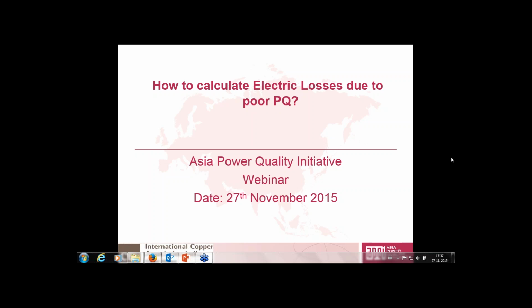Frank, this is for you. From an energy auditor's perspective, how do you calculate the losses due to harmonics and unbalance at any PCC in an industry? Well, the first point is to discover, using something like the unified power method, how to break down into each of the separate components. That's the harmonic and unbalanced losses.